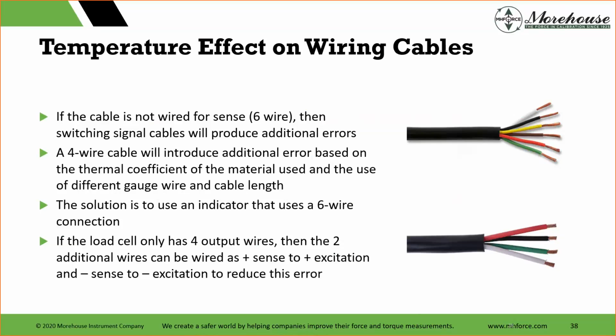The best takeaway here is if you're buying a new system, we have 4215 meters, HADI indicators, our high accuracy digital meters. If you can buy a meter that is 6-wire, you do not need to worry about this additional error. If a load cell or torque cell only has 4 output wires, then the 2 additional wires can be wired plus sense to plus excitation and negative sense to negative excitation. So basically any torsion cell, even if it only has 4 pins, can be wired for 6-wire.